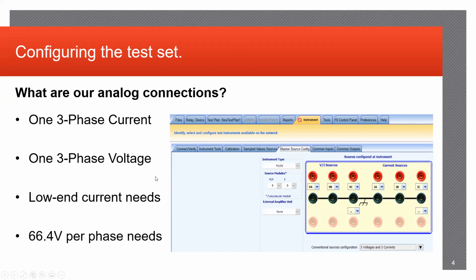Usually, as shown here, it may be a 66.4 voltage source for the AC section. This will change depending on not only the PT ratios that you're going to be utilizing, but as well as what the relay settings basis documents indicate. So you want to correctly identify that all those calculations line up correctly prior to injecting any values or starting any testing, because sometimes you may run into issues such as elements not picking up and you're wondering why, and troubleshooting forever, and then realizing that your source voltages aren't even correct and the relay doesn't even detect it to be properly injected.